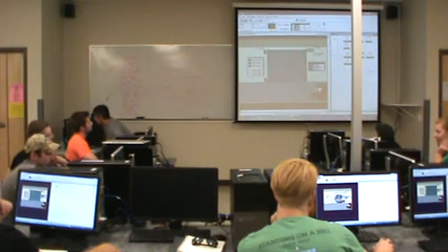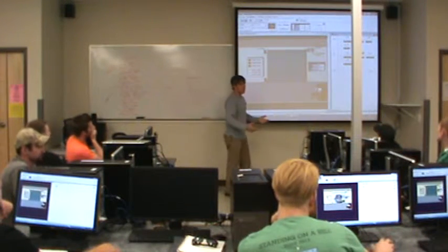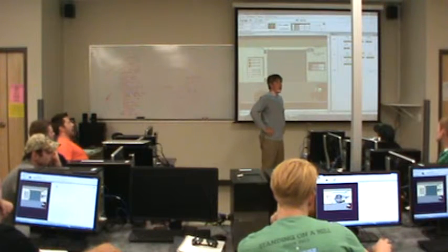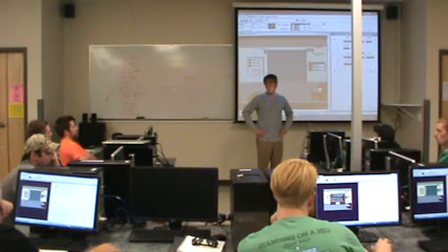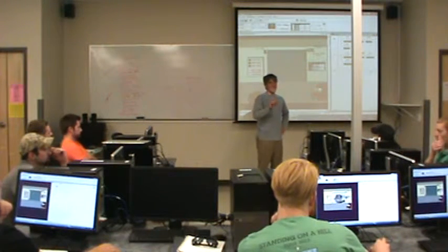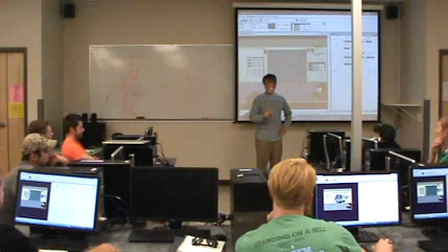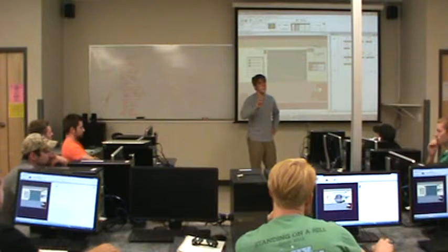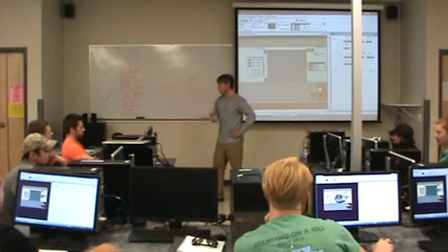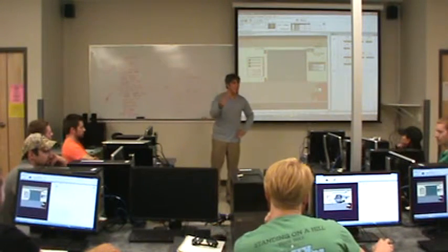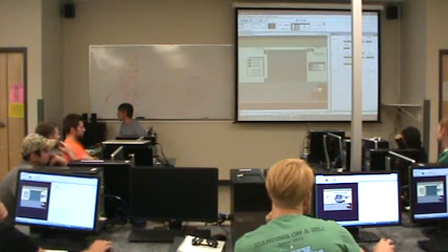Now think with me for a minute. This program would have the exact same problem. If I hit open and I hit close, the motor will catch on fire because both windings are energized. How could we avoid that problem? Basically another condition, isn't it? If the door is moving up, I don't want the down windings to be energized. So the only time that up can go is when down is not going. Okay? On the other hand, the opposite applies for the other direction, okay? So I could put that in as another condition.